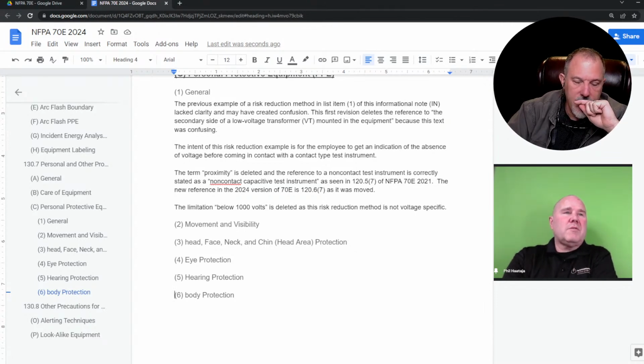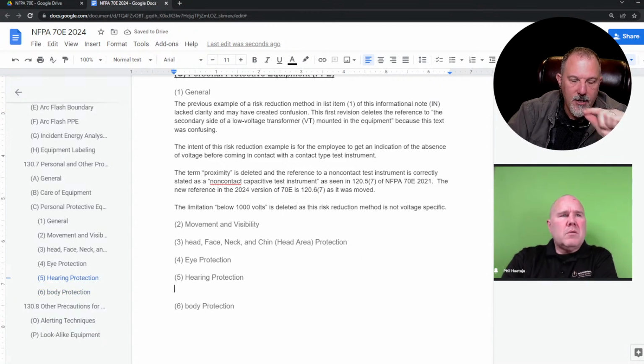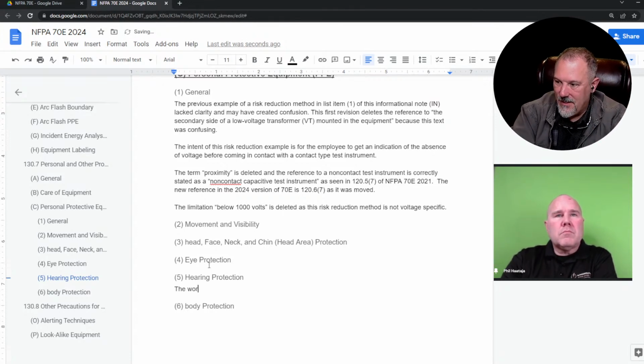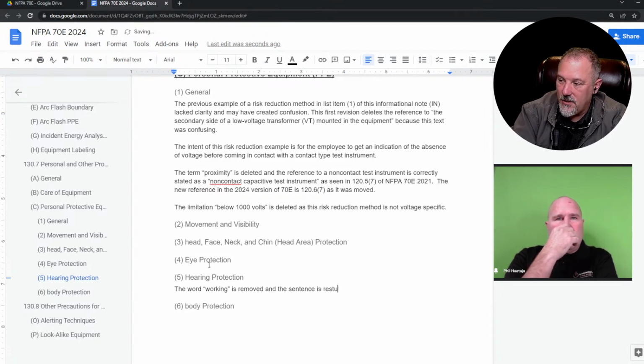Okay, so what changed is hearing protection. What changed in here: employees inside the arc flash boundary shall wear hearing protection. It used to say employees shall wear hearing protection whenever working within the arc. Subtle change, they removed the word working. So the sentence is restructured for clarity.